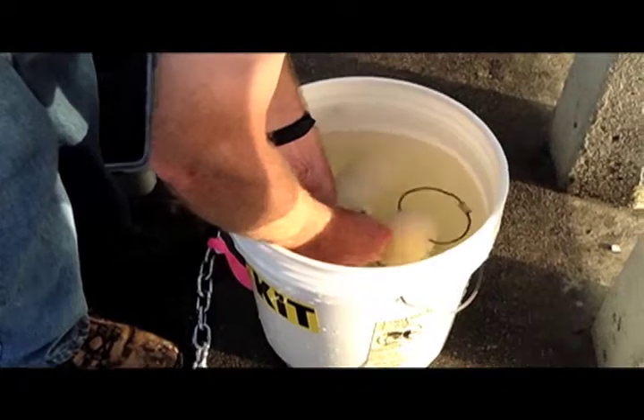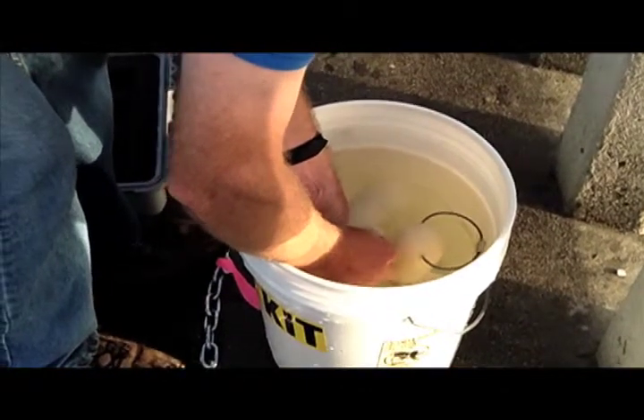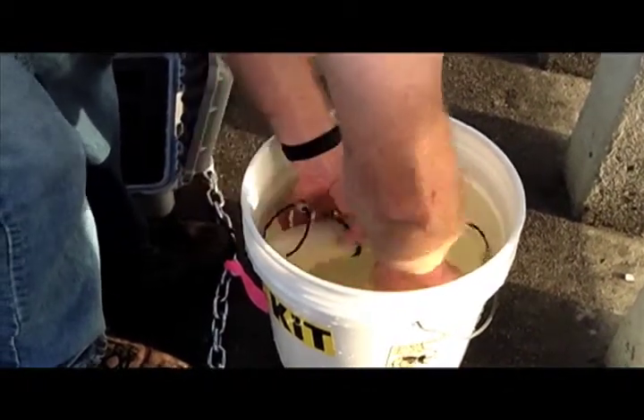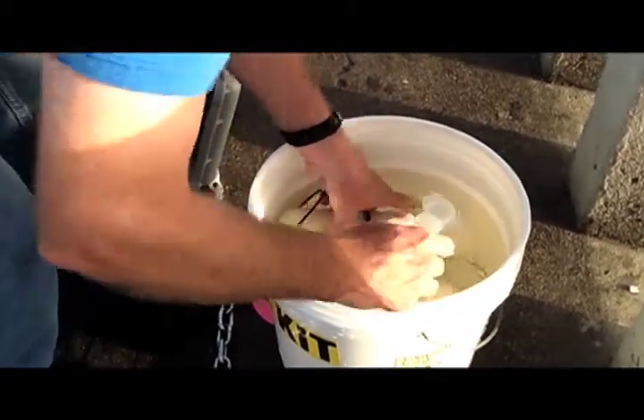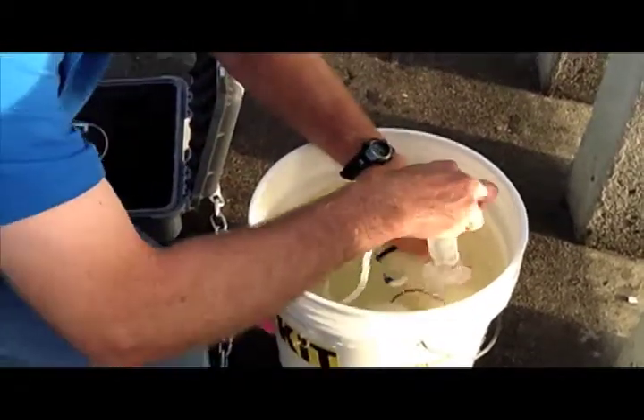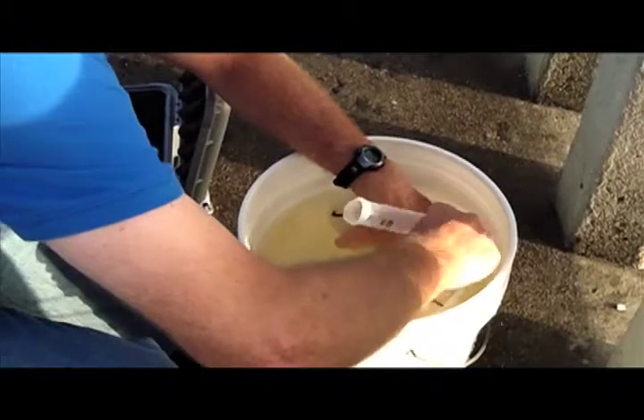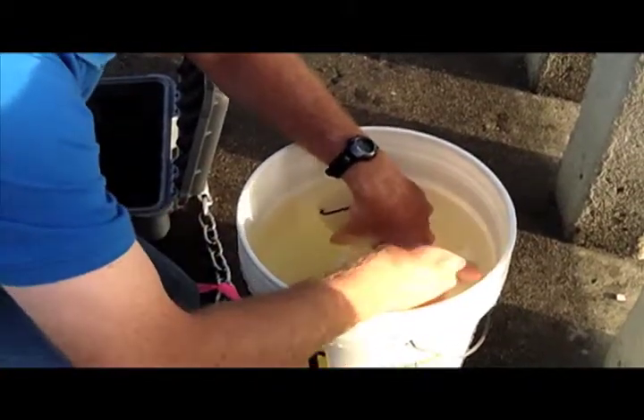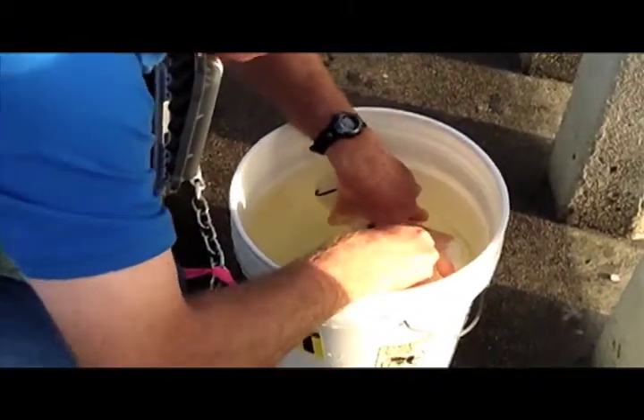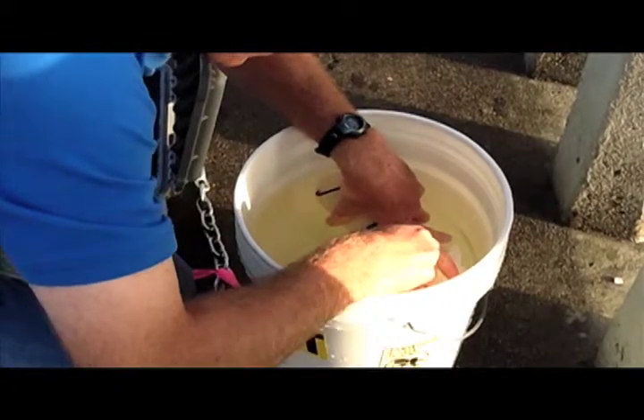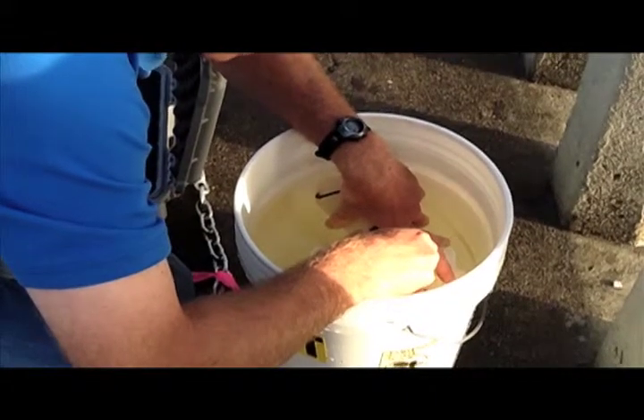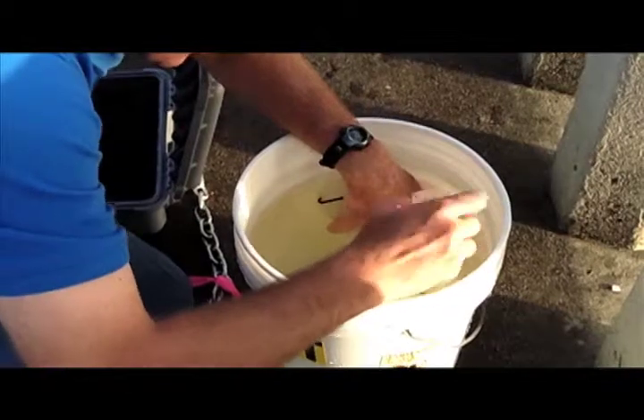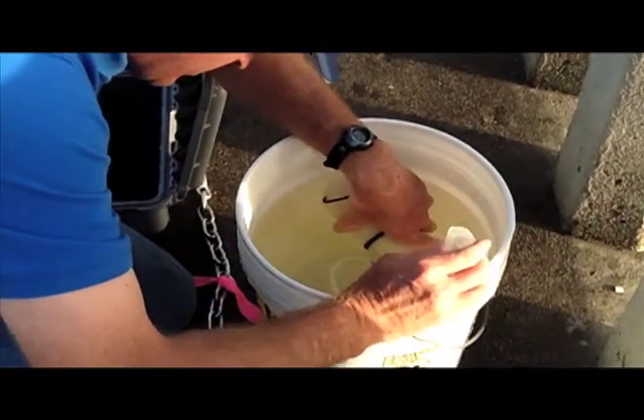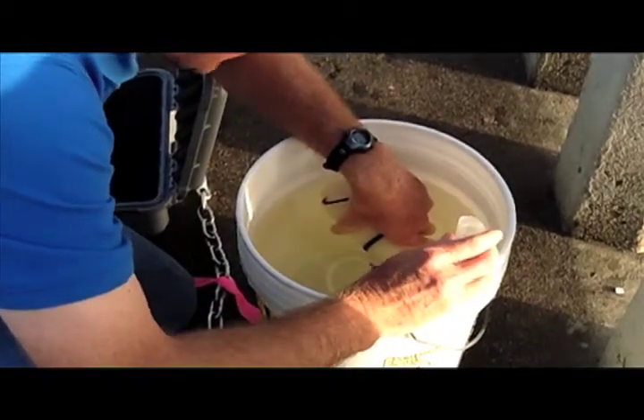Once both units are running, it is now time for the calibration of initial flow rate. Remove the plunger from the syringe included in the Pelican case. The tube attached to the syringe will have a Luer lock fitting on the other end. Attach the tube with this fitting to the outlet fitting on the side of the CLAM while keeping the CLAM completely submerged. Shortly, you should see water coming into the syringe.